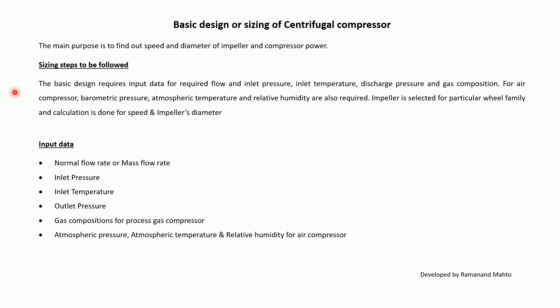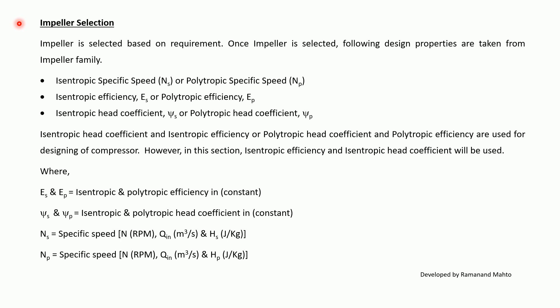The input data required includes normal volumetric flow rate or mass flow rate, inlet pressure, inlet temperature, output pressure, and gas composition for gas compressors. For air compressors, we need atmospheric pressure, atmospheric temperature, and relative humidity. The impeller is selected based on the requirement, and once selected, the following design properties are taken from the impeller family: isentropic specific speed, polytropic specific speed, isentropic efficiency, polytropic efficiency, isentropic head coefficient, and polytropic head coefficient.